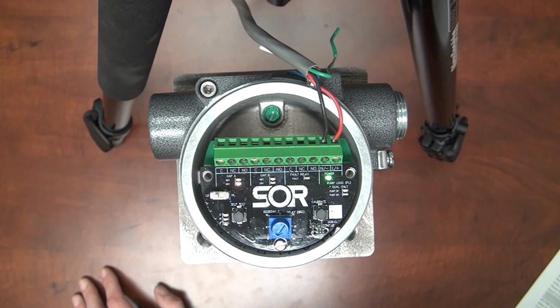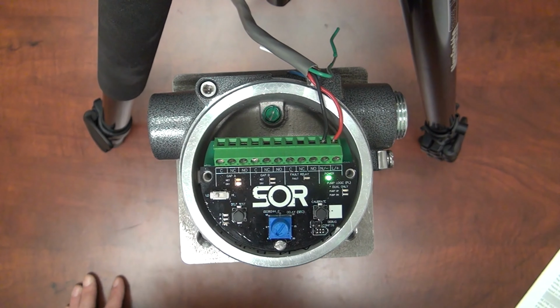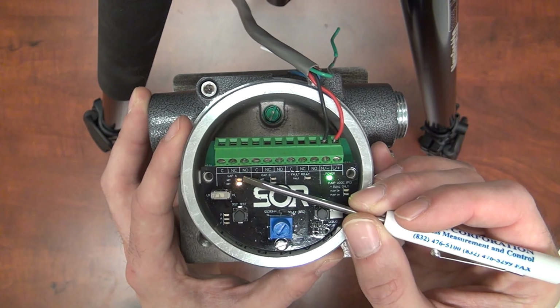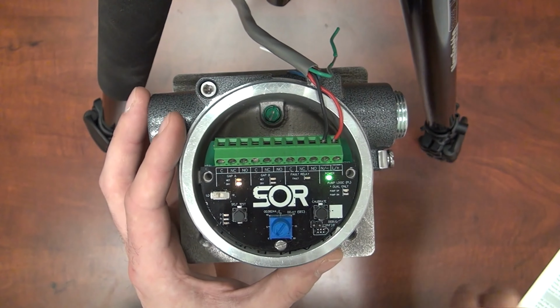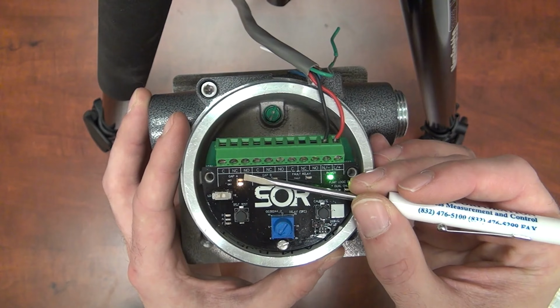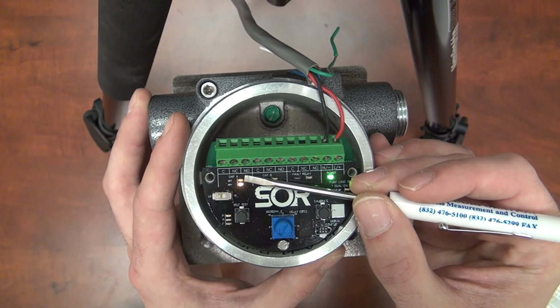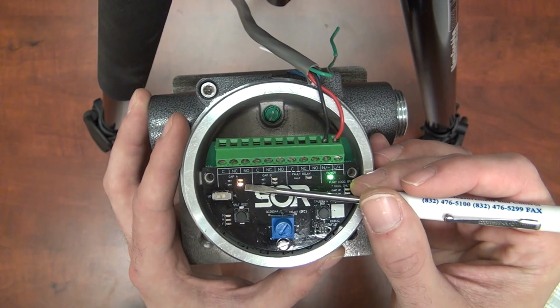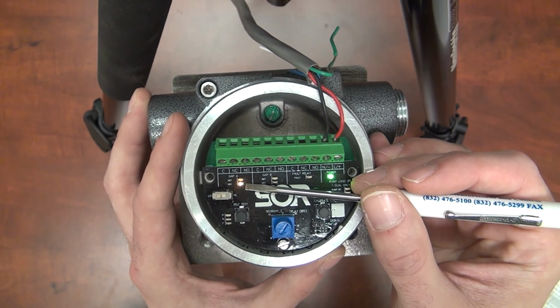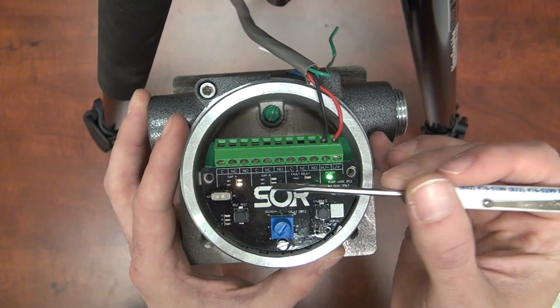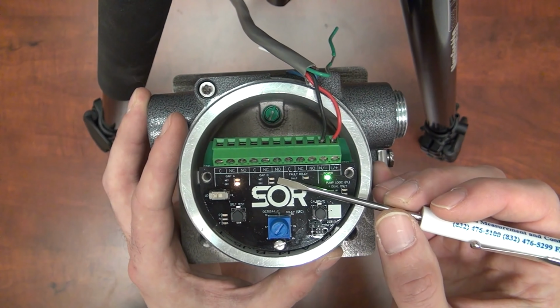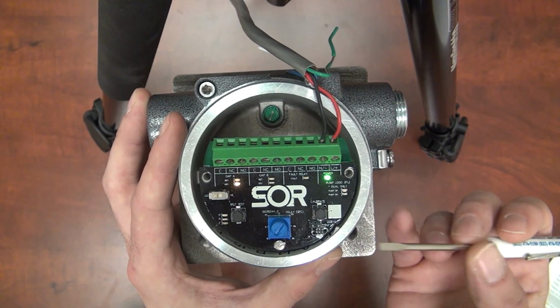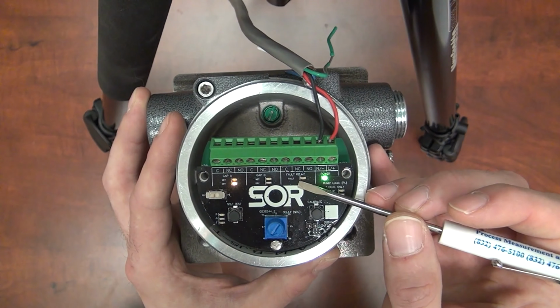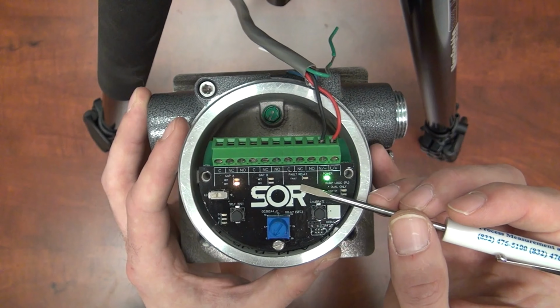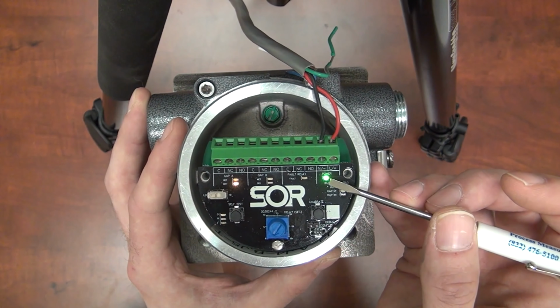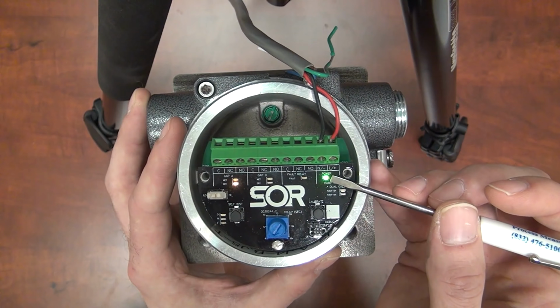Now let's look at the LEDs. Starting with the LEDs below the terminal strip. Up first, we have the wet and dry LEDs for each gap. The wet LED is blue and indicates if there is liquid present in the cavity. The dry LED is amber and indicates if there is an absence of liquid in the cavity. The same colors are used here for gap B, though those will only be seen on dual point units. Next up we have the fault relay, this single red LED here. If this is on, this indicates a fault. And then lastly we have the power LED here, lit green, indicating that the correct amount of power is being supplied to the device.